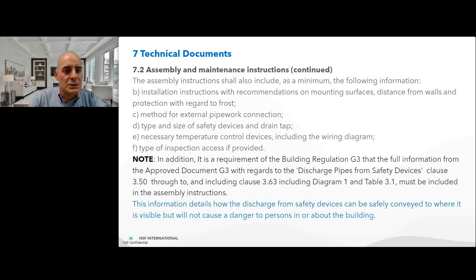The assembly instructions shall also include a minimum of the following, so installation instructions with a recommendation on mounting surfaces, distance from walls and protection with regards to frost, method for external pipework connection, types and size of safety devices and drain tap, necessary temperature control devices, including the wiring diagram, and types of inspection access if provided.